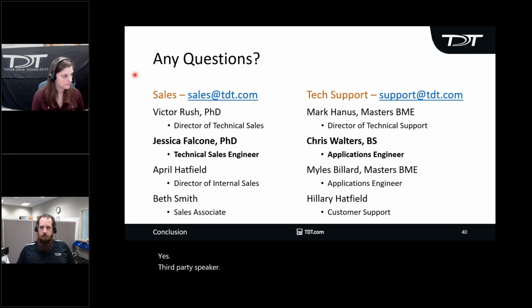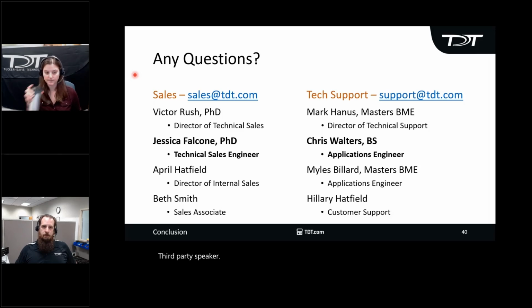It's just a matter of making sure that you have a good calibrated microphone, and that you have fixed distances, and you make sure that all of the other configurations are correct, and you can use any speaker, either a TDT one or an external one that you've purchased yourself for calibration.